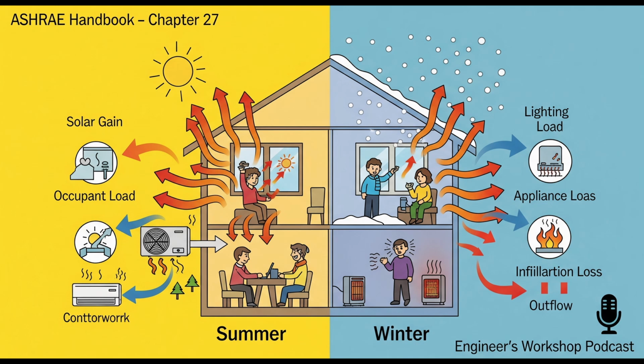And those calculations determine how big your furnace or AC needs to be, how much it costs to buy and to run. If you understand fenestration and account for it properly in the load calculation, you might be able to use a smaller, cheaper, more efficient HVAC system - lower energy bills, and a home that actually stays comfortable. If you ignore it, you risk an oversized system that cycles on and off too much, doesn't dehumidify well, and wastes energy, or an undersized one that can't keep up on the really hot or cold days. It's fundamental to getting the design right.